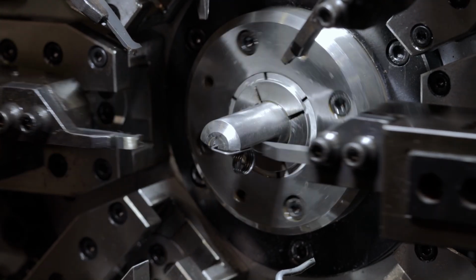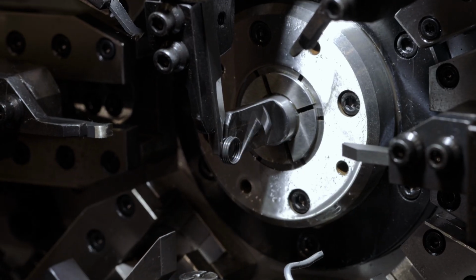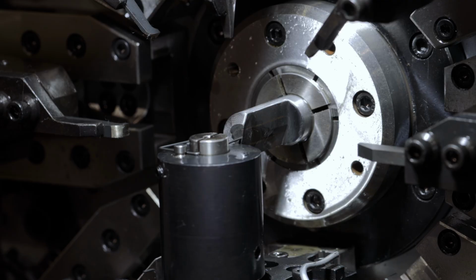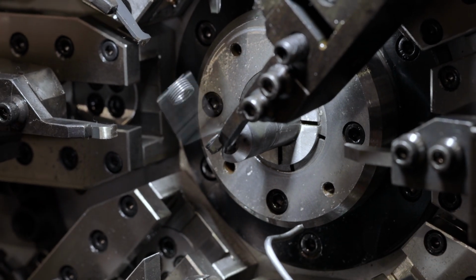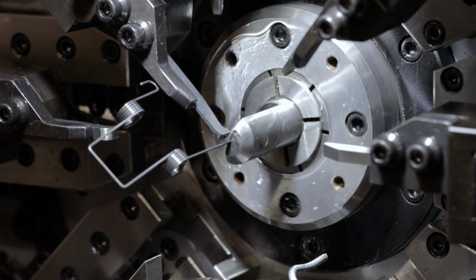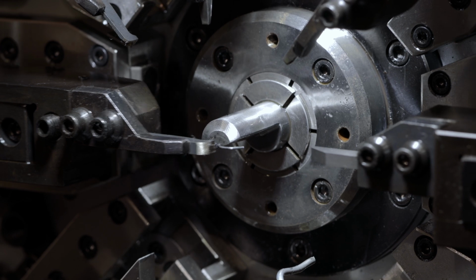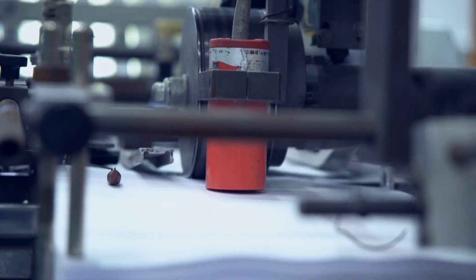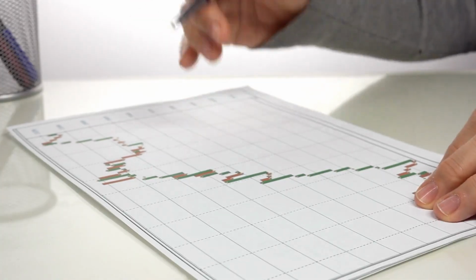Poor mounting during installation can also introduce misalignment, adding unnecessary stress to the bearing and surrounding components. Additionally, exposure to sanitation chemicals, water, and contaminants can degrade bearing materials and cause corrosion, especially in environments where cleanliness is critical. Understanding these factors and identifying their early signs allows us to address wear before it turns into a costly failure. This is where vibration analysis comes into play.